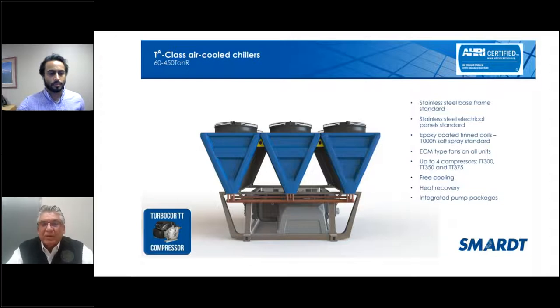So not only water cooled, but air cooled. If you look at Smardt from an air cooled performance perspective, very low dB levels. Every machine comes with stainless steel base and a base rail, and ECM type condenser fan motors as well, which helps with regulating and modulating the amount of head pressure. It also provides a great application for free cooling and heat recovery.